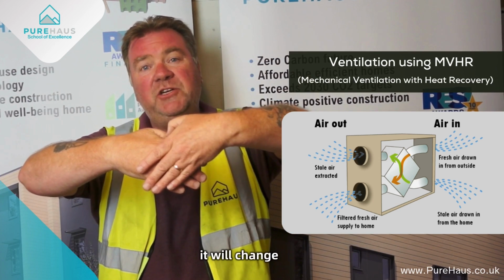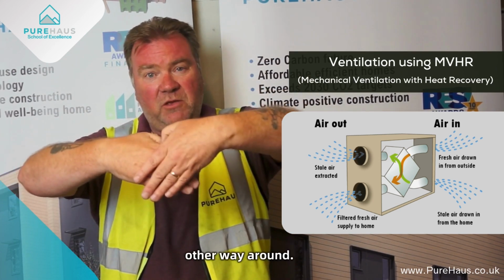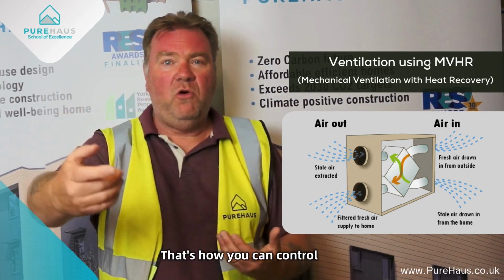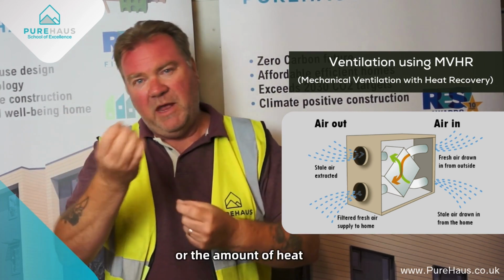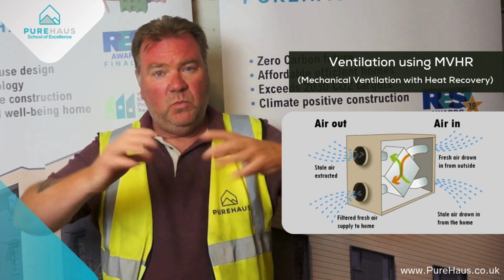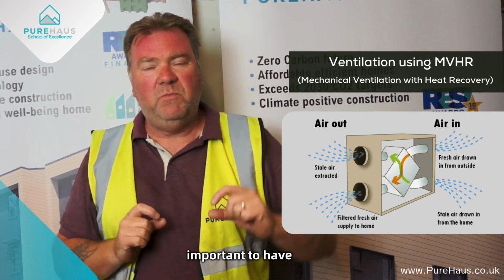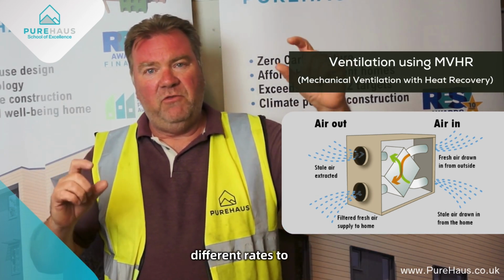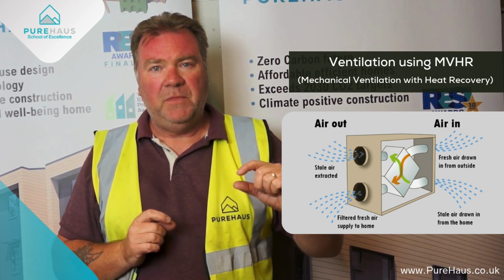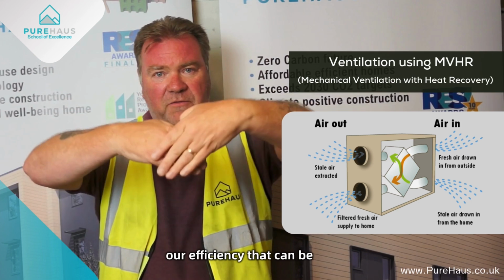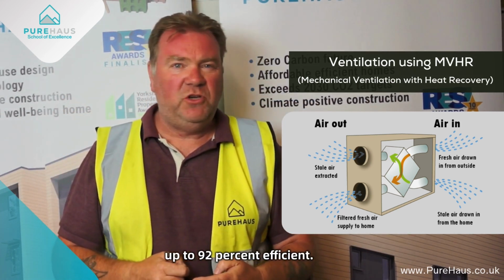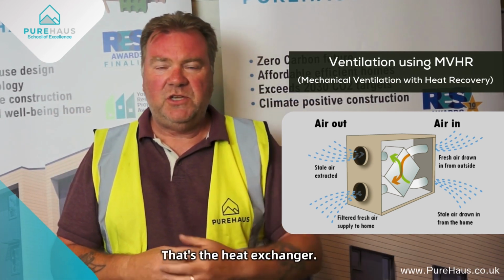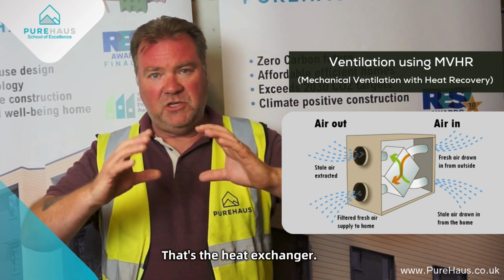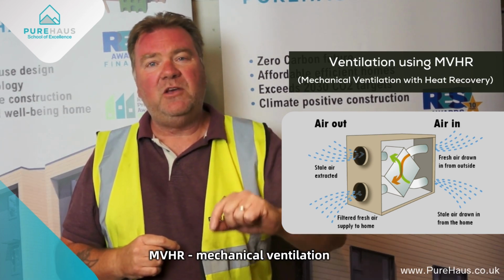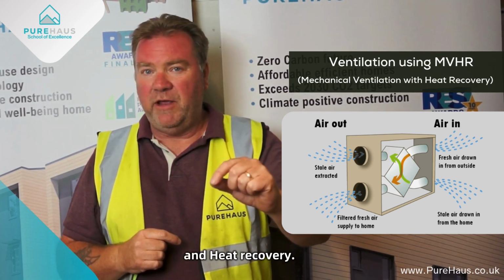So if this is faster and that is slower, it will change at a different rate as if it was the other way around. That's how you can control the amount of energy or the amount of heat that is exchanged within that heat exchanger, which is why it's important to have different airflows at different rates, two independent fans. So that is how we get our efficiency. That can be up to 92% efficient. That's the heat exchanger. MVHR, mechanical ventilation and heat recovery.